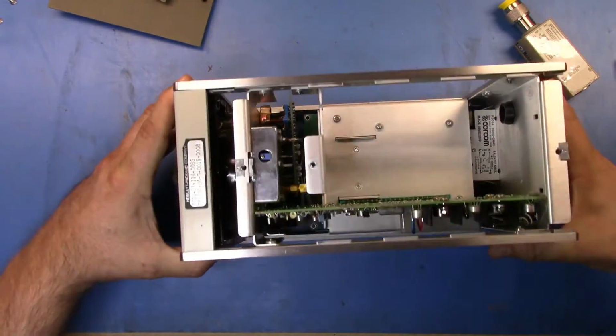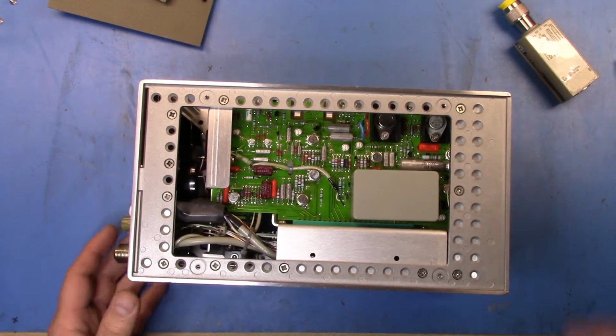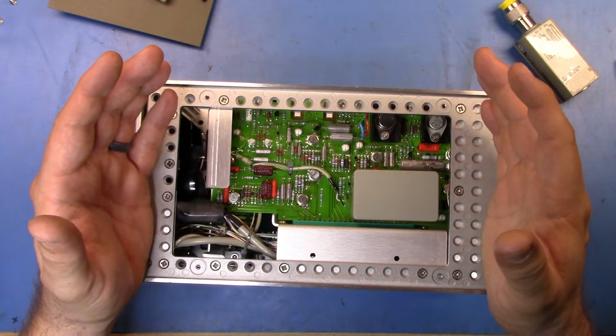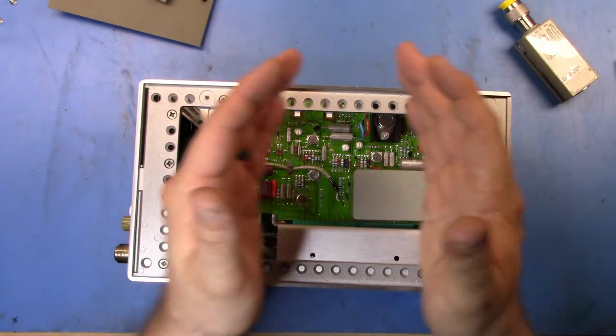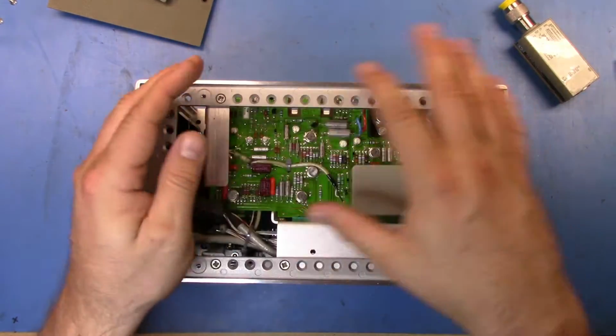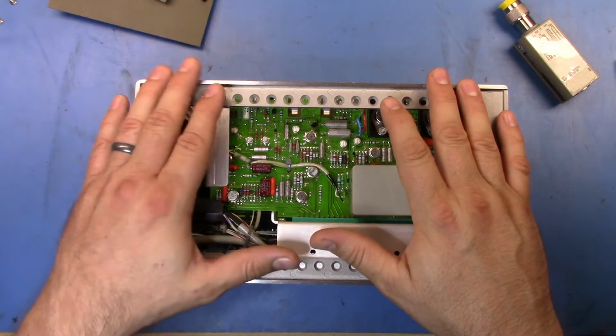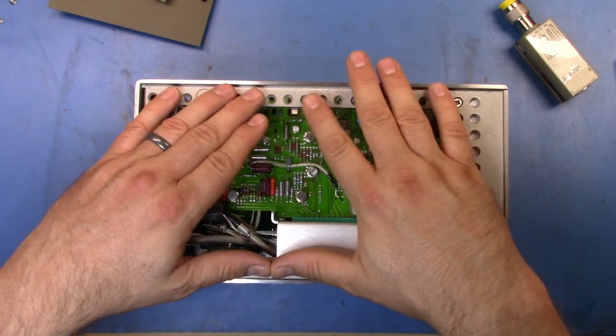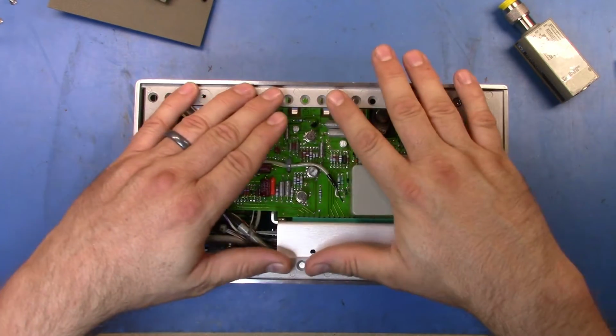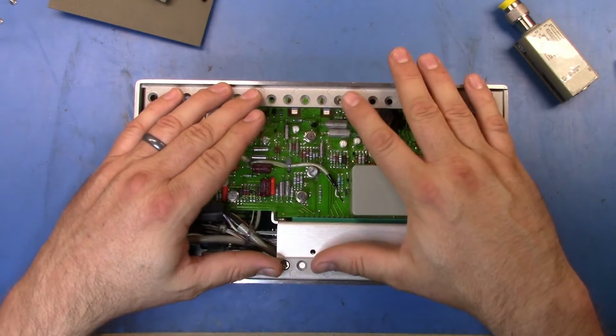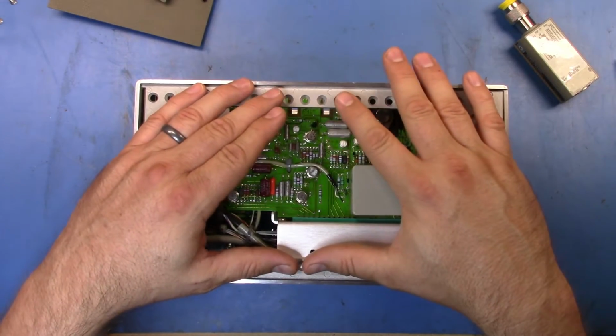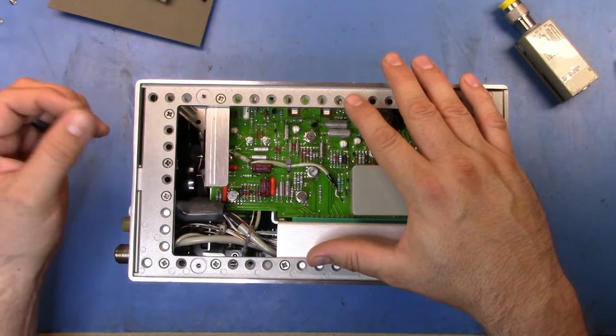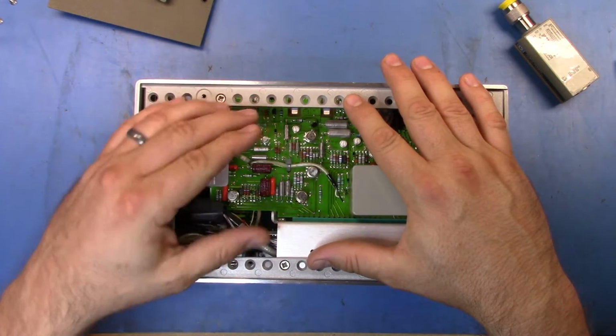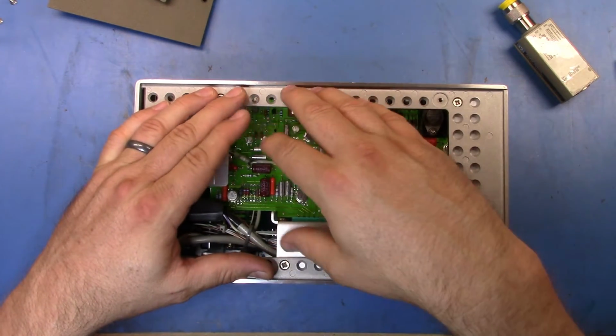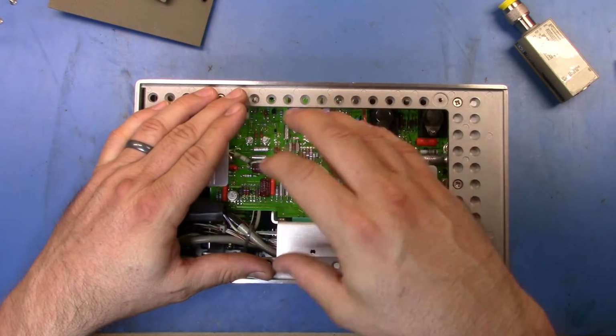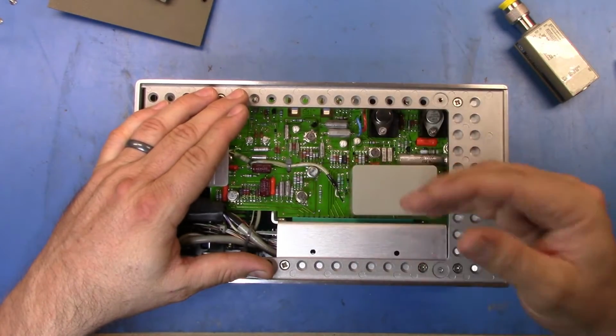Anyway, that's that guy there. Let's have a look at the side here. What you've got is this circuitry, basically a chopper amplifier with multiple stages before it pumps out the final value on the meter. If you've seen a 419 or looked at how Fluke or HP gear of this era was built, it's very hard to make a DC amplifier that's very accurate and linear, so it was much easier to make an AC amplifier. So they would take a DC signal, run it through a chopper, and the chopper would cut the signal up to basically create an AC signal out of the DC value. Then they could feed that through the amplifier stages and very accurately amplify that AC signal. At the end, they demodulate it and come out with the final DC value.